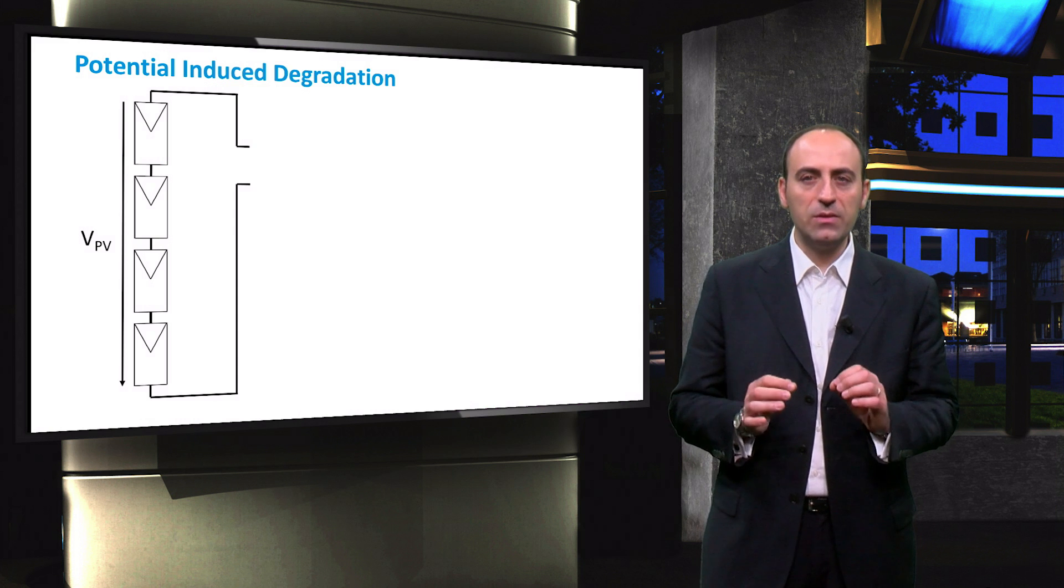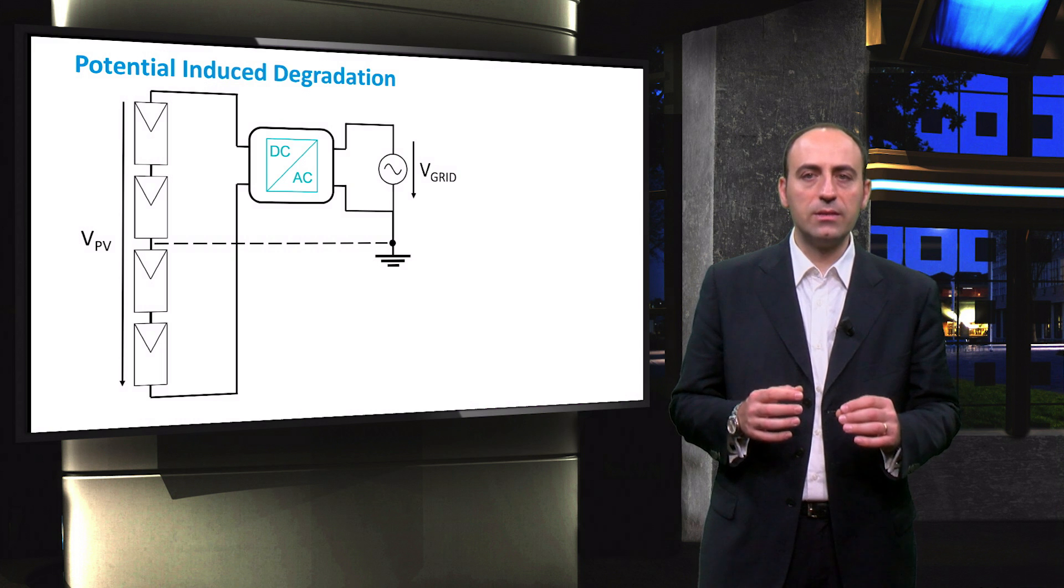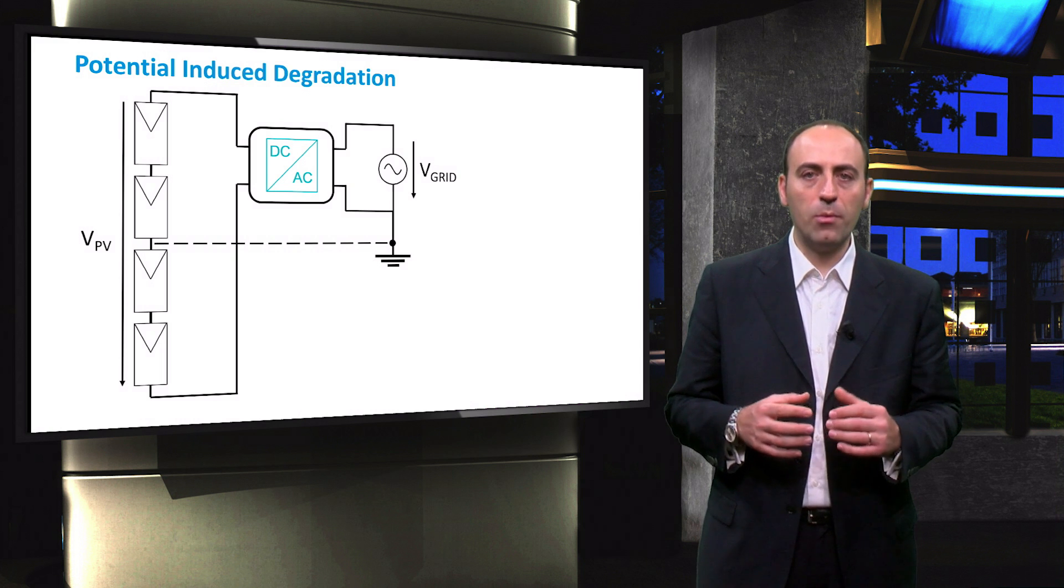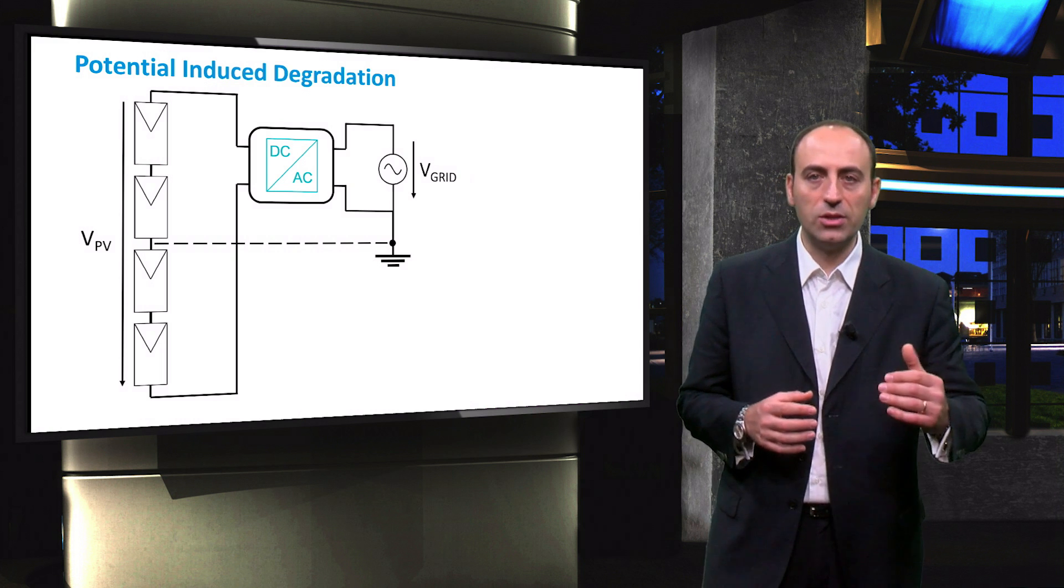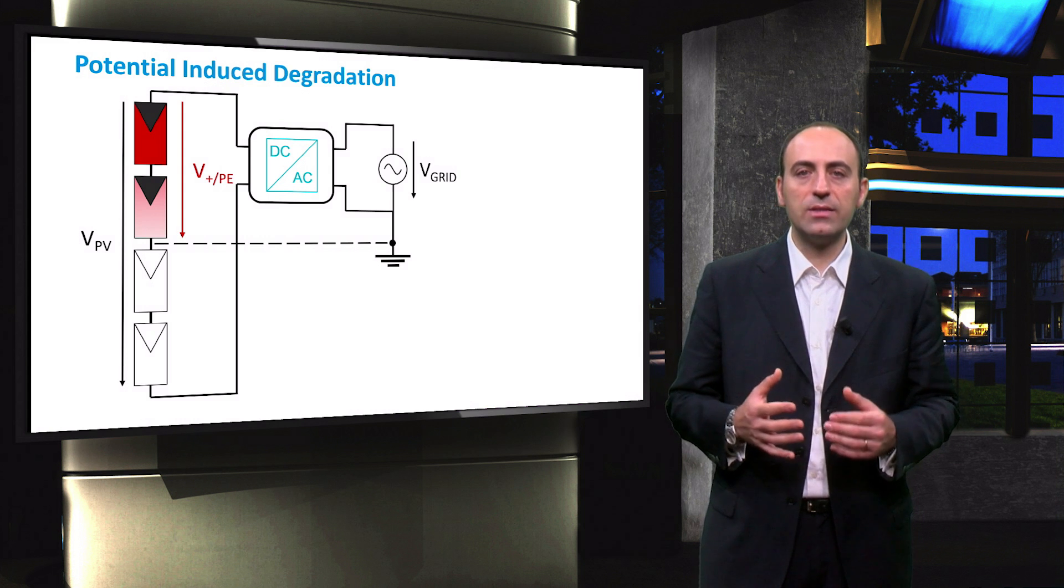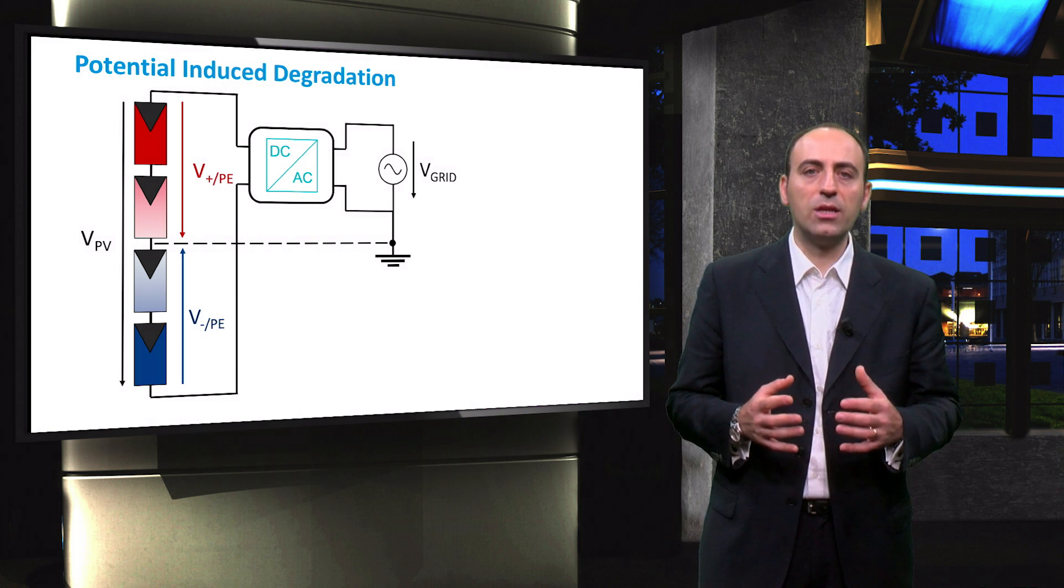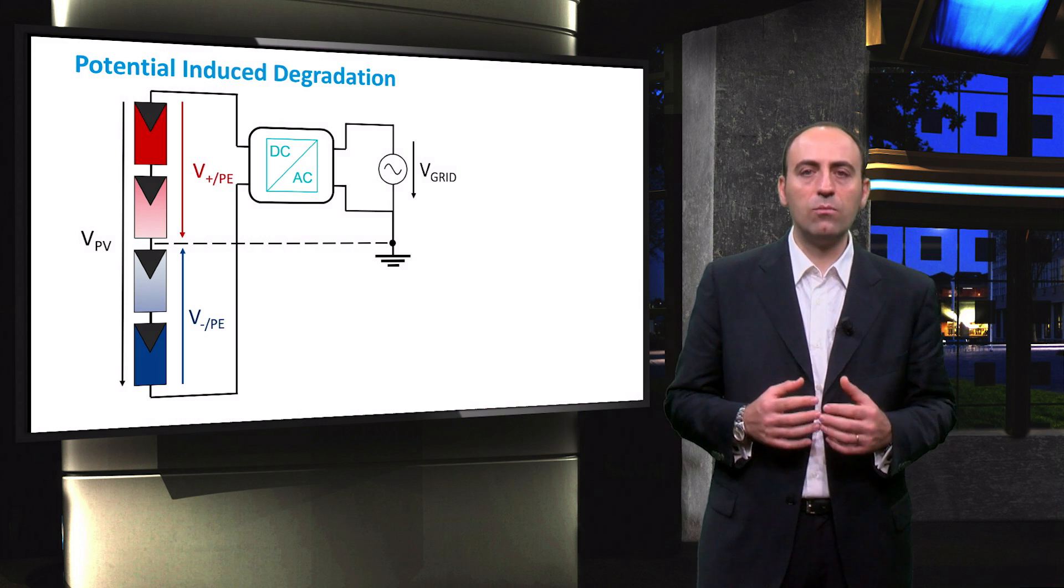Let's take a PV system connected to the grid via an inverter. The neutral point is in the middle of the system, so a positive pole shows a positive potential or a voltage against the ground. In a similar way, there is a negative pole.